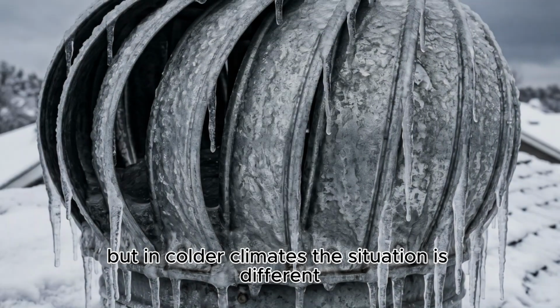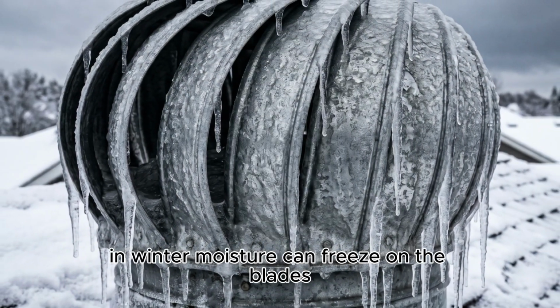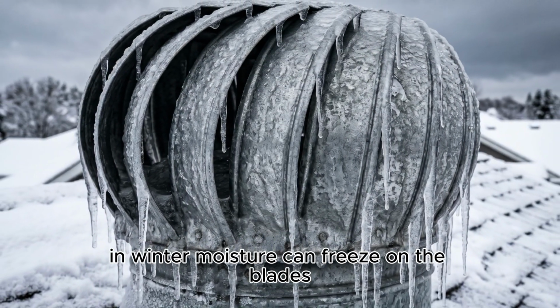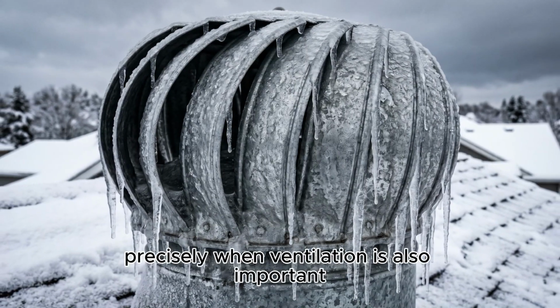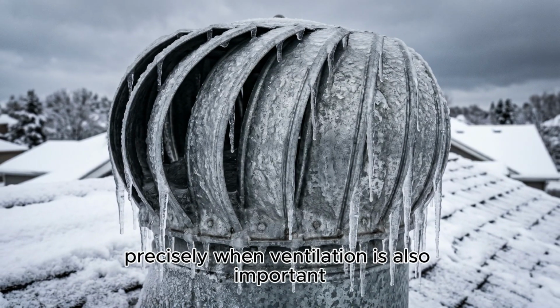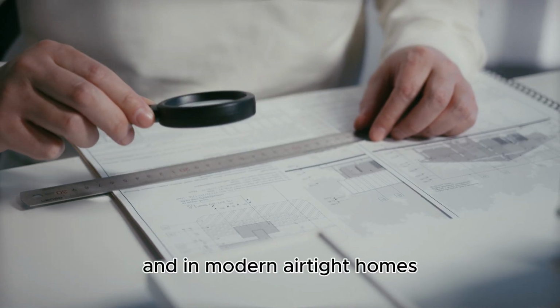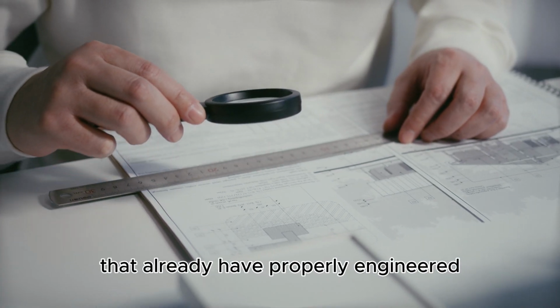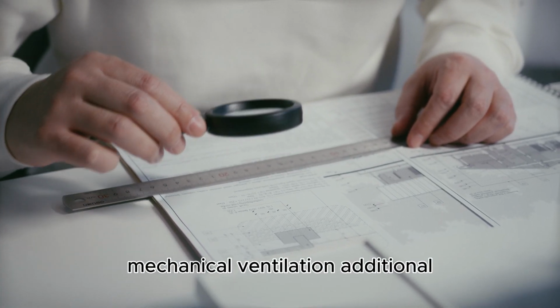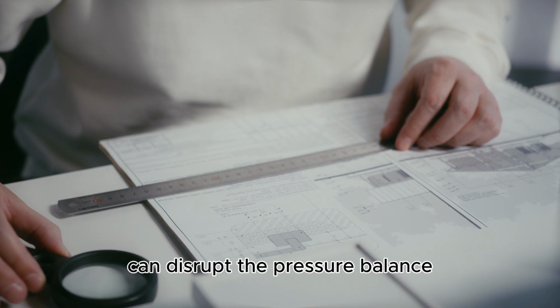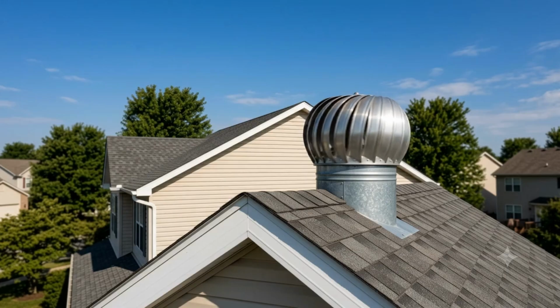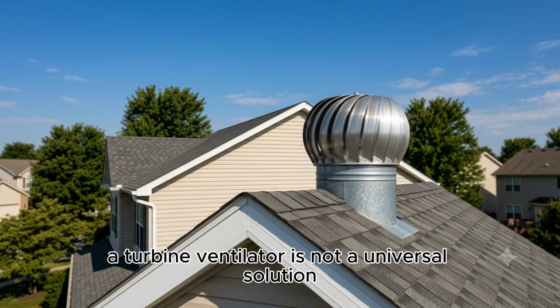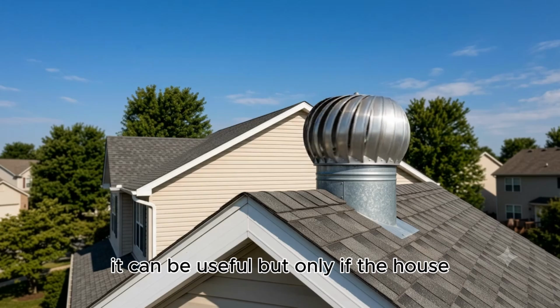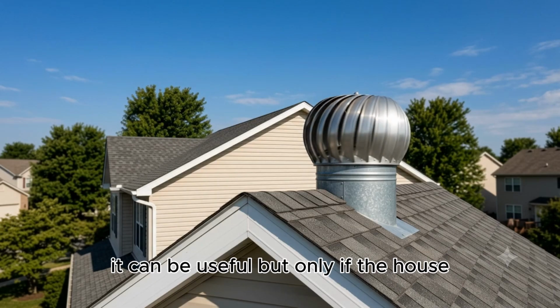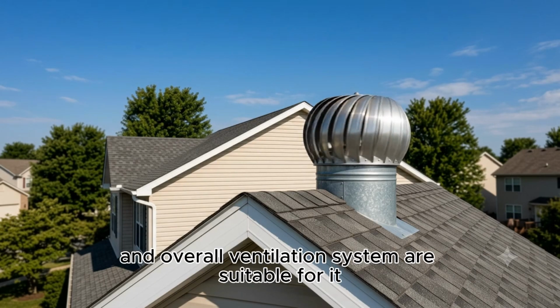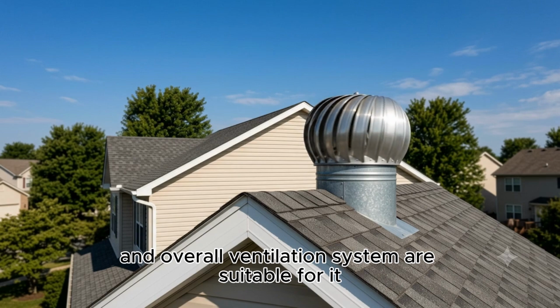But in colder climates, the situation is different. In winter, moisture can freeze on the blades. The turbine can stop operating precisely when ventilation is also important. And in modern airtight homes that already have properly engineered mechanical ventilation, additional passive exhaust ventilation can disrupt the pressure balance. In other words, a turbine ventilator is not a universal solution. It can be useful, but only if the house, climate, and overall ventilation system are suitable for it.